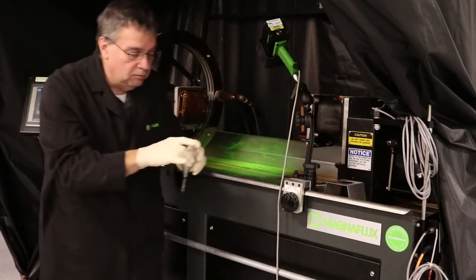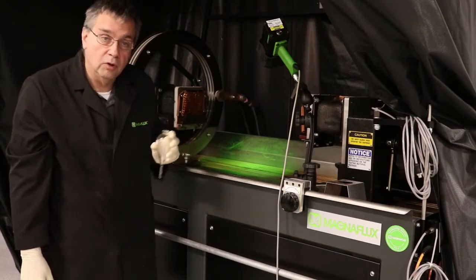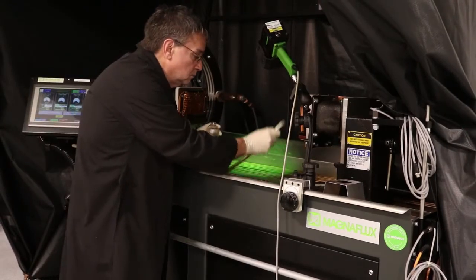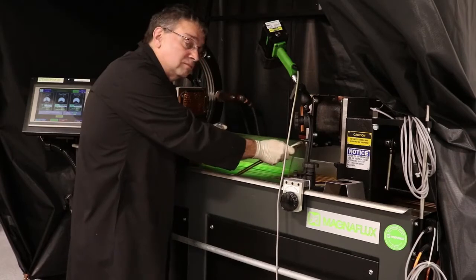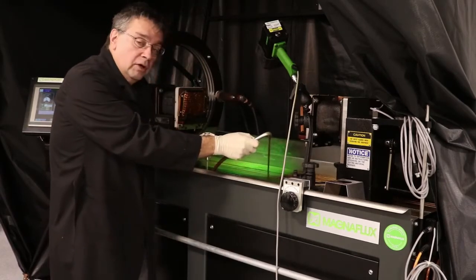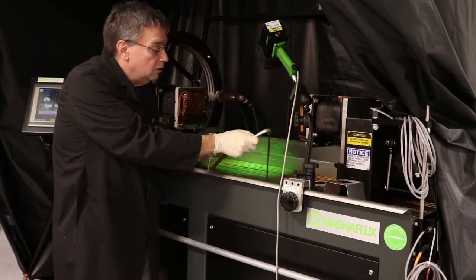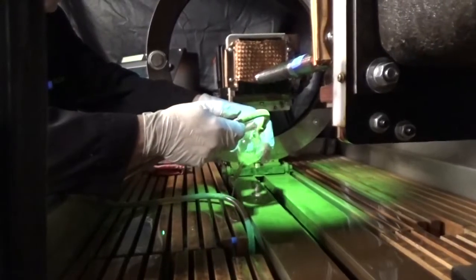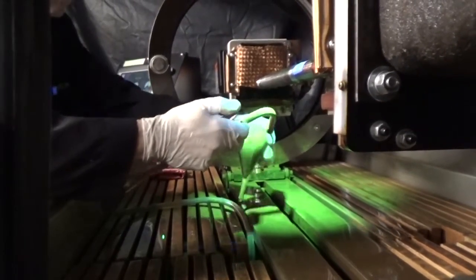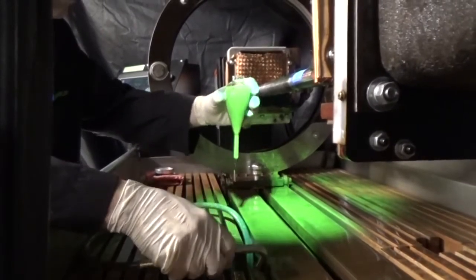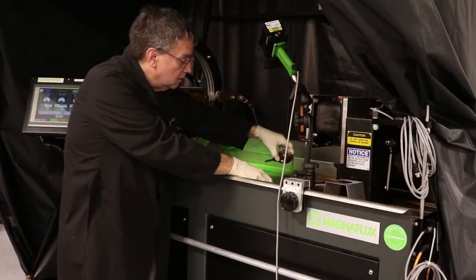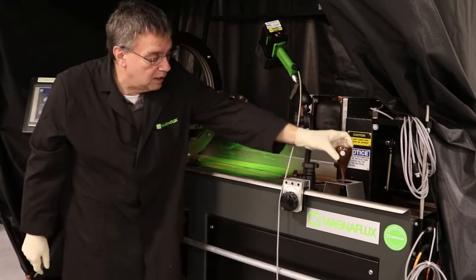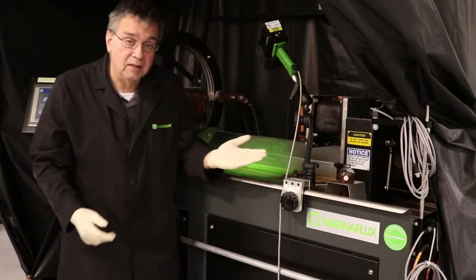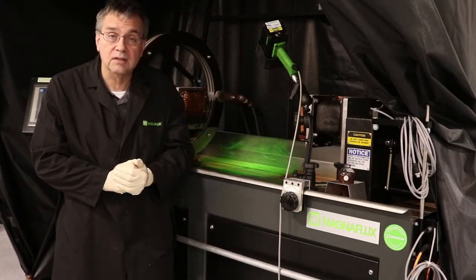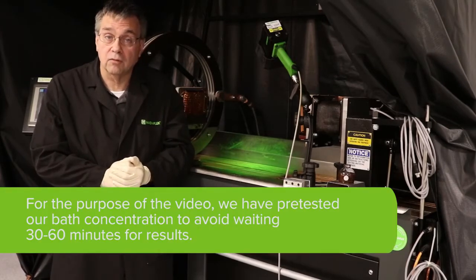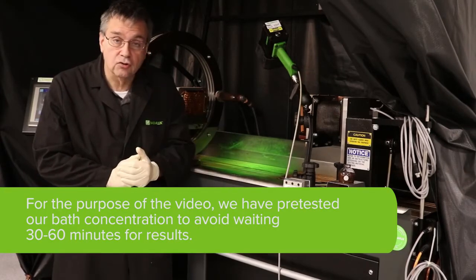We'll need a centrifuge tube, the one appropriate for the particles and fluid you're using in your bath, and your pump has been running. You run fluid through your bath hose until you get particles coming out, and you fill the centrifuge tube up to 100 milliliters. After that, you place the centrifuge tube in a stand and let it sit. If you're using an oil bath, it has to sit for at least 60 minutes. If you're using a water bath, it is only for 30 minutes. And then you read the concentration.